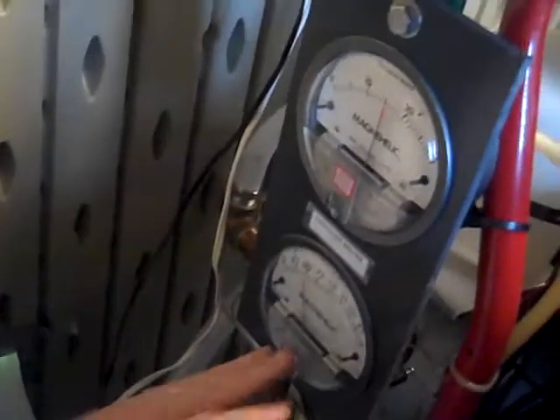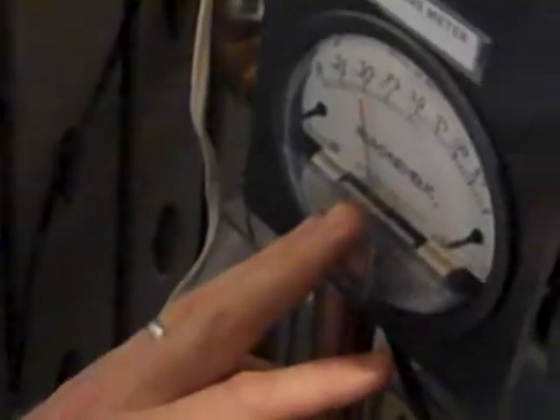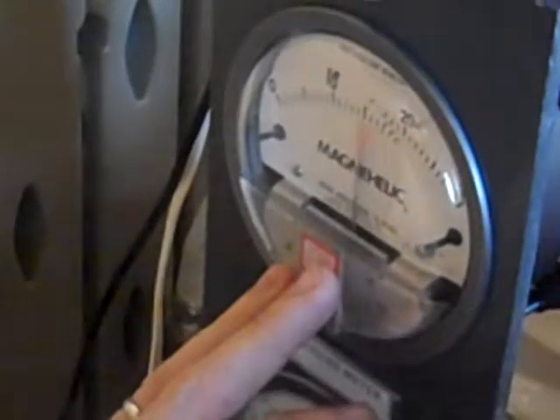Okay, the other things we want to check out are the Magnehelic. So right now, our target is to have the bottom Magnehelic, which is measuring flow at 0.5 inches of water, and the top Magnehelic, which is measuring system pressure at about 15 inches of water. If the flow rate's off, there's a handle which we'll go over and look at that we can use to adjust to get the right flow rate to 0.5. Okay, so let's go over to the other side and look at what we have to look at over there.